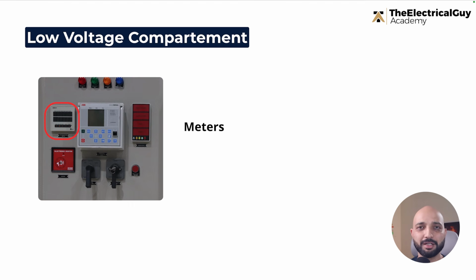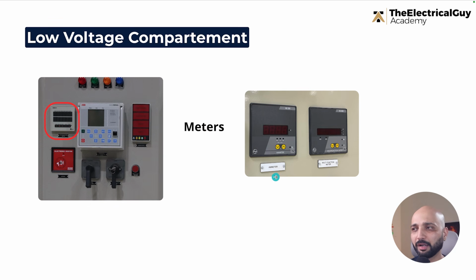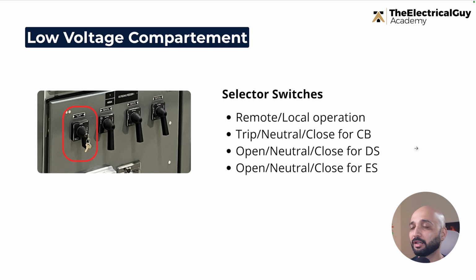Then of course you will also find meters. We can have multifunction meters, or we can have dedicated ammeters and voltmeters. Here you can see a multifunction meter is provided. When we say ammeter or voltmeter, they are specifically designed to give you the voltage and current. A multifunction meter can give you a lot of things, including power factor. You will very commonly find meters on the low voltage compartment. In fact, you will also find revenue metering in some of the panels, especially the meters that we see inside our homes, to monitor the electrical consumption. So those are meters.